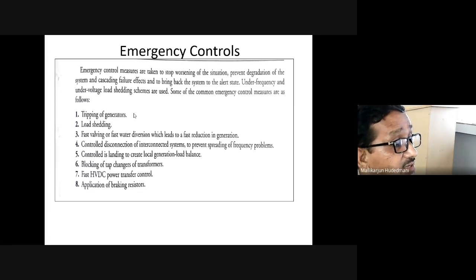Like this, in an emergency, it is critical that the decision is to protect the generator. The rest of the system or other parts of the connected system have already worsened, gone out of your control. At least save this. This kind of tripping of generator would be one choice. Load shedding. The load is so massive on this. Suddenly, in steps or in a proper mechanism, remove the load so that the load is isolated from the generating area and at least the generation setup is safer from that perspective. This is how load shedding, removal, works. Scheduling is reorganizing; shedding means exactly removing it.